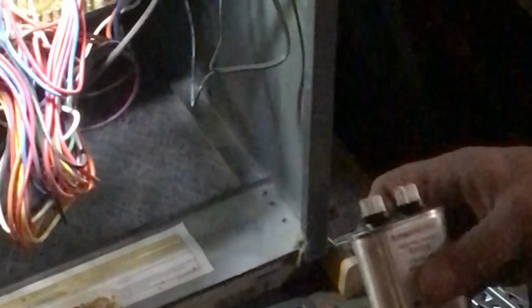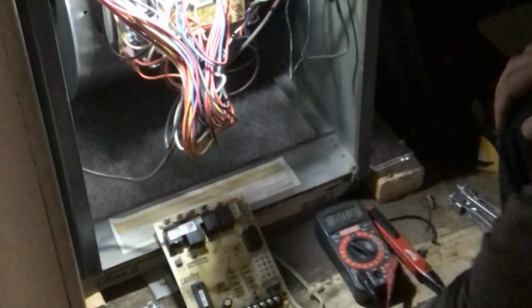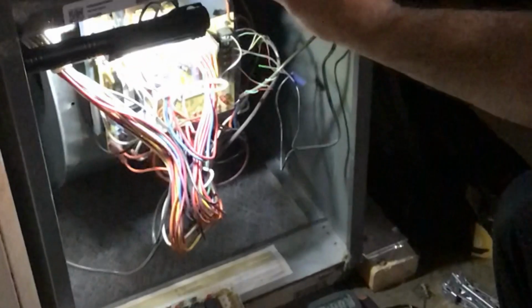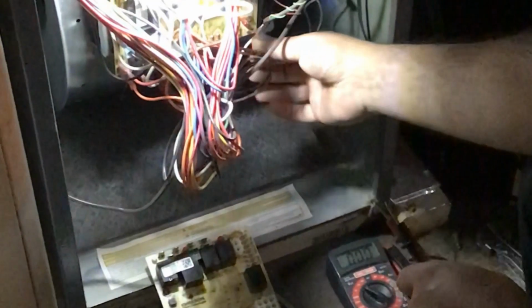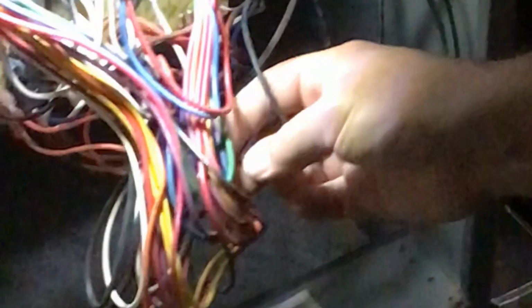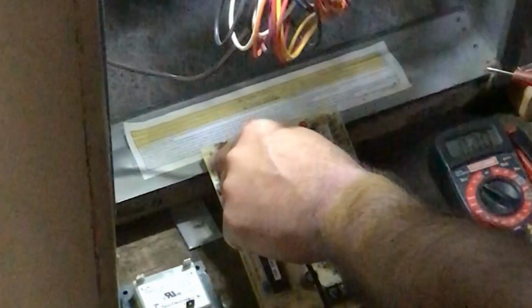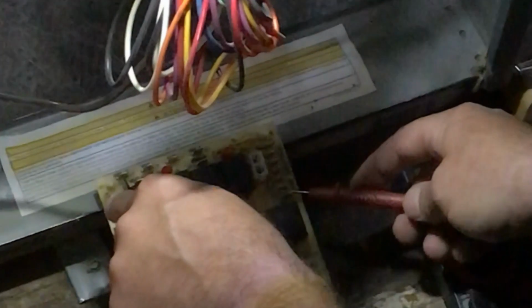But before you replace this, there's one other check to do if your indoor blower is not operational. And there's two ways you can do it. One's a little fast shortcut. The other way, you can test on the board if you only have a multimeter. So, assuming that your door switch is depressed, assuming that we have 120 volts to the furnace and everything is energized, what you want to test for, you want to disconnect your black wire, that's your high speed wire, from the fan to the circuit board. And that wire should go to a terminal that says cool. And just like we tested before, you want to test to that cool terminal and to a neutral or any known ground.